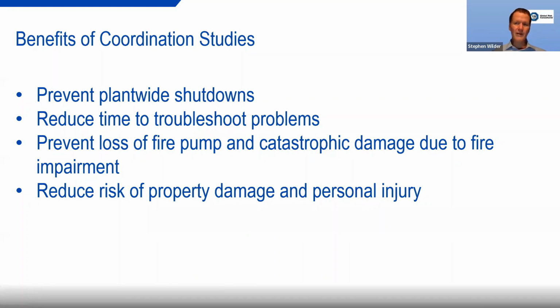So let's say you own a large industrial plant. If the coffee maker in the office overheats and trips the breaker, do you want to trip the breaker that just feeds that kitchen circuit, or do you want to trip a breaker upstream and lose millions of dollars a day because the whole plant shut down or critical equipment shut down? If the whole plant shuts down, how do you know which breaker tripped? It's going to take a long time to troubleshoot each breaker in the plant.